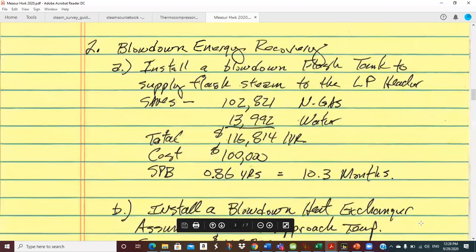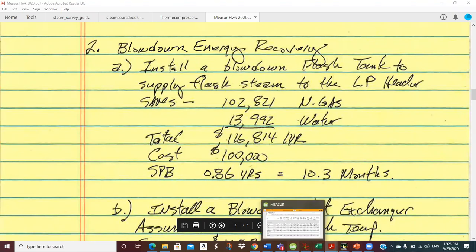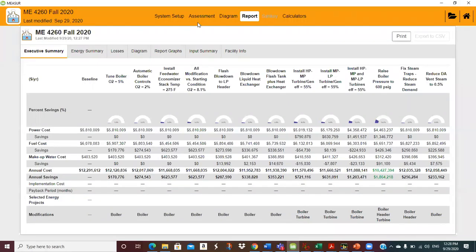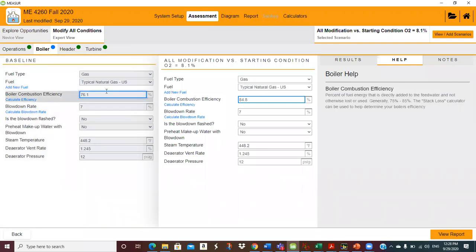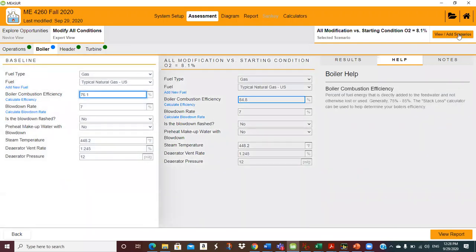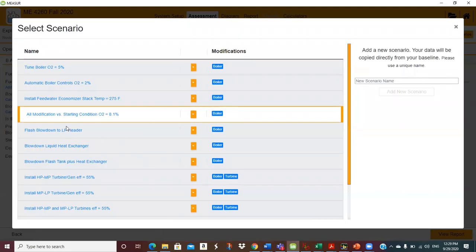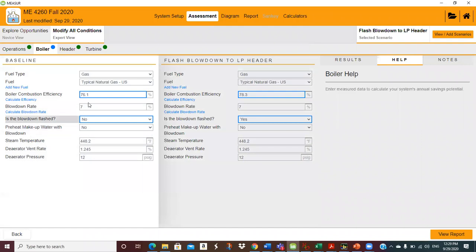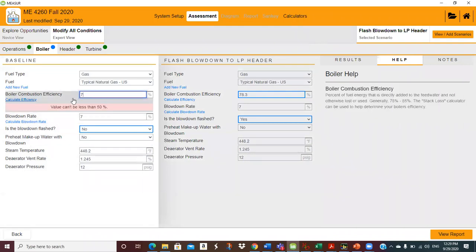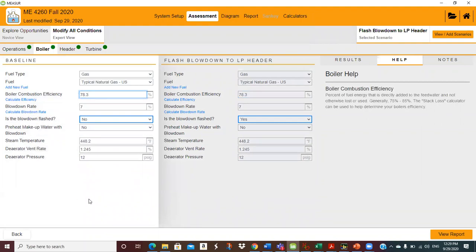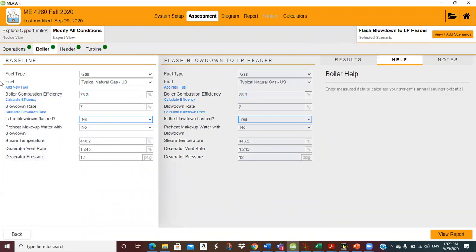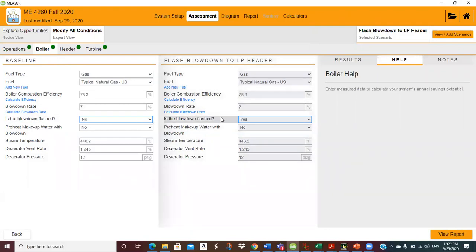Let's go to blowdown energy recovery. I think we said to assume the boiler had been tuned, so we've got to set — let me call up the scenario. We're going to do the flash tank first. I think this was 78.3% boiler efficiency. Let's see — boiler: is blowdown flashed? No. Yes.